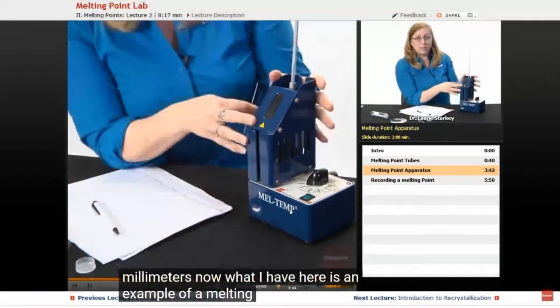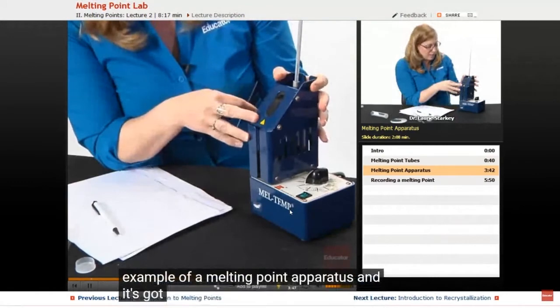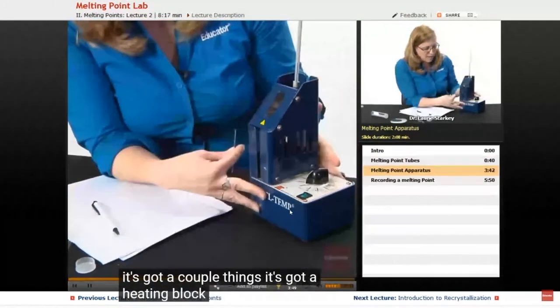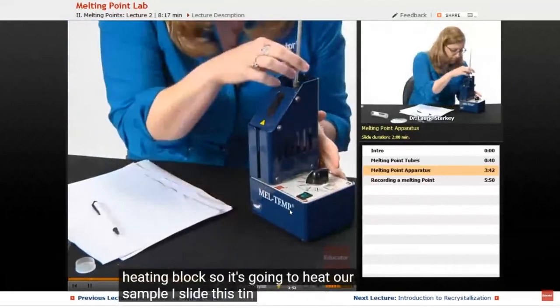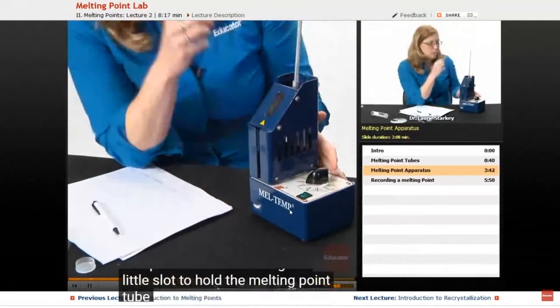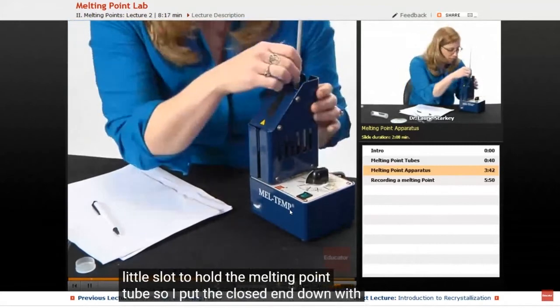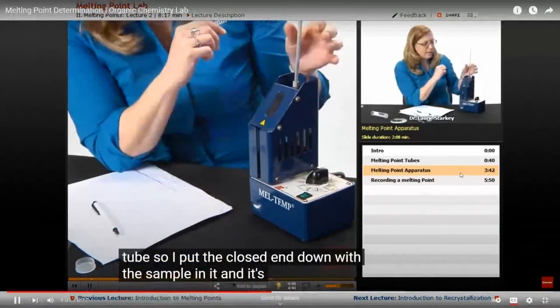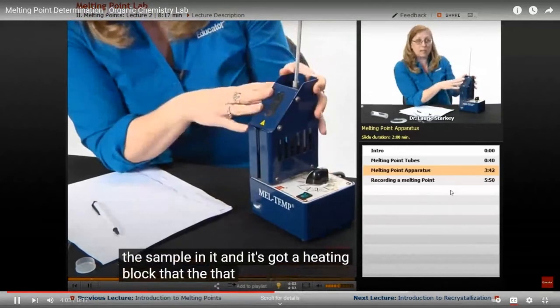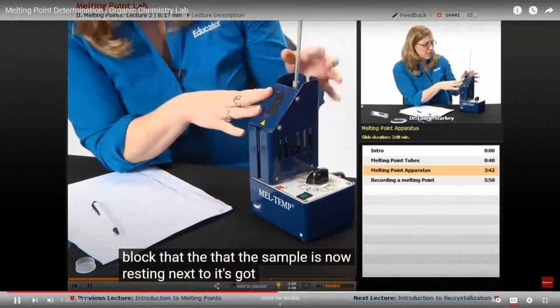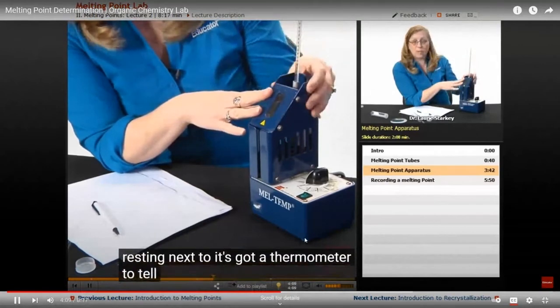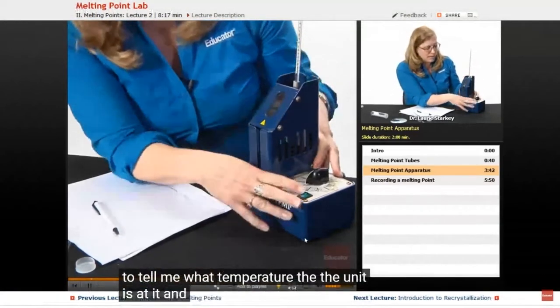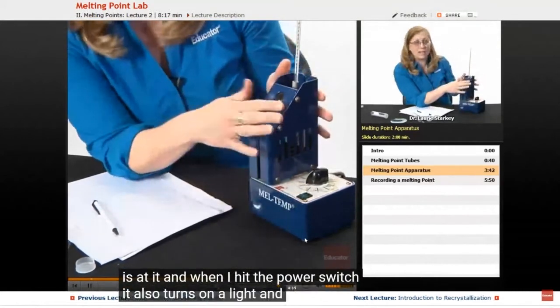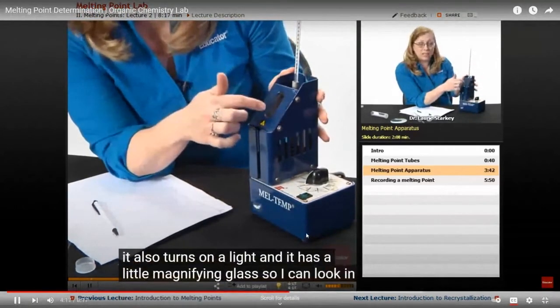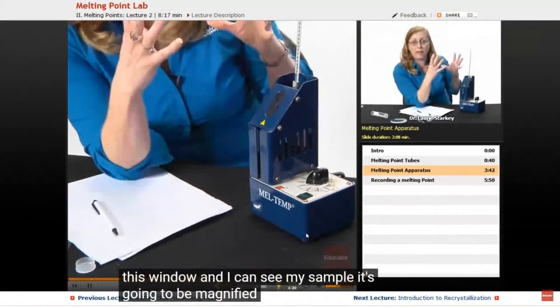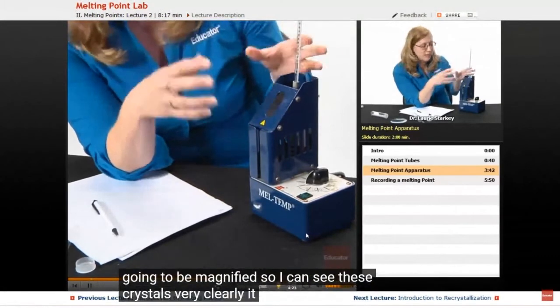Now what I have here is an example of a melting point apparatus, and it's got a couple things. It's got a heating block, so it's going to heat our sample. I slide this in. It's got a little slot to hold the melting point tube, so I put the closed end down with the sample in it, and the sample is now resting next to the heating block. It's got a thermometer to tell me what temperature the unit is at. When I hit the power switch, it also turns on a light, and it has a little magnifying glass, so I can look in this window and see my sample. It's going to be magnified, so I can see these crystals very clearly.